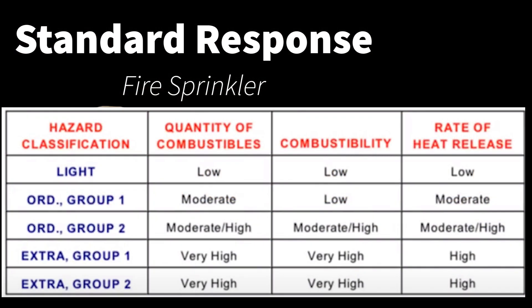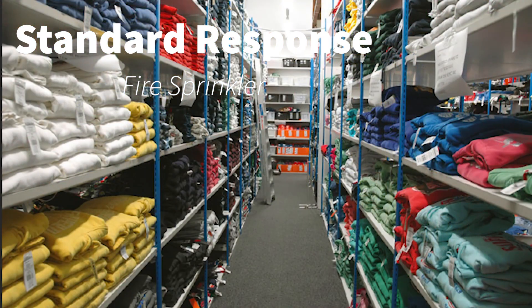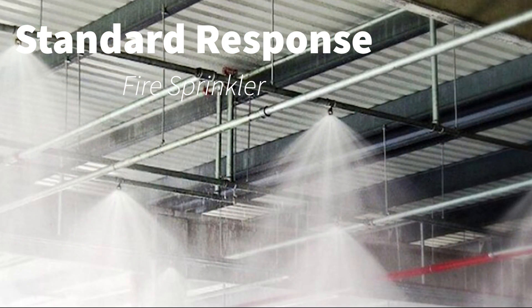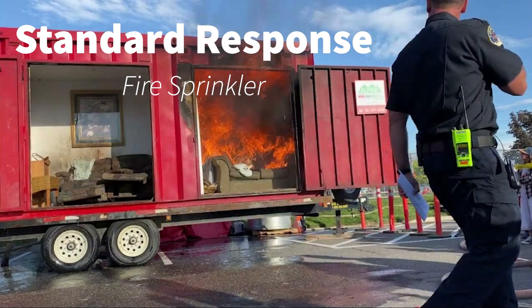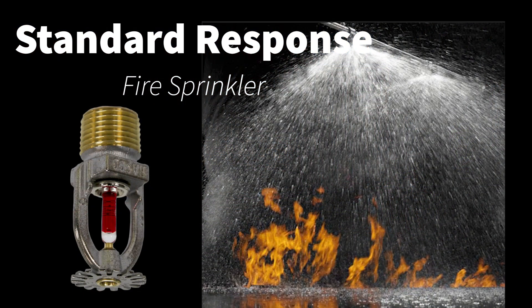When ordinary hazard's combustibility and rate of heat release goes to moderate and high — ordinary hazard group two — you will use the standard response head. Examples are retail stores and storage rooms. The reason for switching to standard response is that higher combustibility and heat release can cause too many quick response heads to operate at the same time, which is very taxing on the system's pressure and causes the spray pattern to be less effective. A smaller number of heads operating in the correct locations with the correct pressure gives much better results in controlling the fire — as proven in live fire tests.